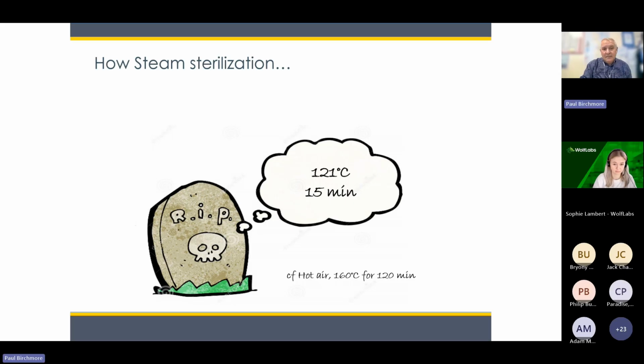And you can do it with air, but as I just touched on, there's no vaporization, there's no condensation, there's no change of state. So hot air is by no means as effective. You'd have to do it for longer and at a higher temperature to get the same result. So that's why steam is such a popular, well-known and well-used method for sterilization.